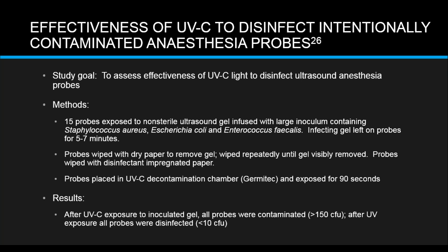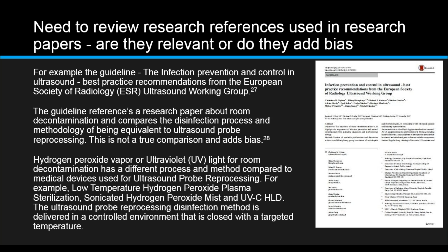Need to review research references used in research for bias. We talked about that. This was a recent guideline, and what they tried to do in this guideline was extrapolate from the very robust literature of UV disinfection devices in rooms to UV disinfection devices for probes. And I said they're not relevant. It's not a fair comparison. In rooms, don't forget, energy from UV light falls off with the square of the distance. So you may be trying to disinfect things that are 2, 3, 4 meters away and may not be in direct line of the UV. Whereas when you put a probe into one of these UV disinfection devices, you're millimeters to centimeters away, and there is really no shadowing. And the energy level, of course, is much higher because the distances are much closer.